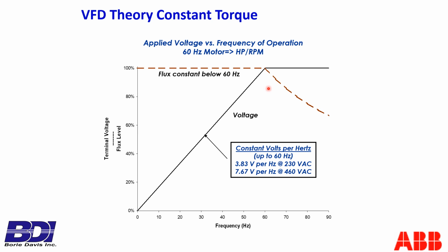Well, that means I could take that speed up, so long as I don't cross this torque line, and I'll run satisfactorily. So we can increase frequency above 60 hertz and run the motor faster, but we have to realize right here at 60 hertz, there's no more horsepower available. If it was 5 horsepower, this is where I'm getting 460 volts at 60 hertz and whatever the load is, that's what I am.